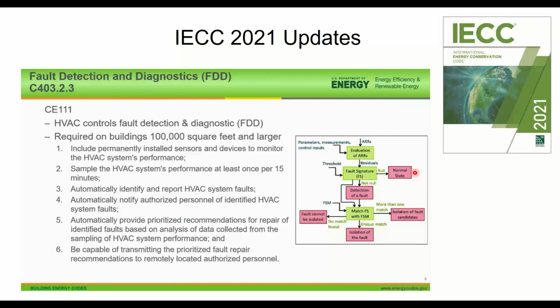Other stuff that's happening, most of you have done or been involved with or aware of that we have fault detection and diagnostic requirements on economizers today. We've had those for the past 4 or 5 years in the energy code. That means if the economizer has an issue, such as actuators binding up, it has to self-detect the issue and then report it to someone. Not just by turning on a light inside the unit that no one sees. It's got to send it to the building automation system, or if there's no BAS, send it downstairs and make it flash on the thermostat. So we have that on economizers for a while.